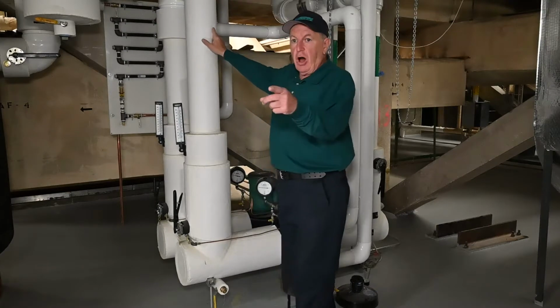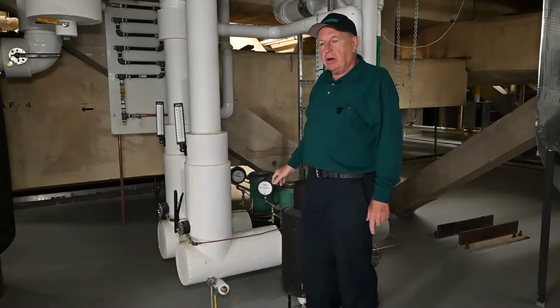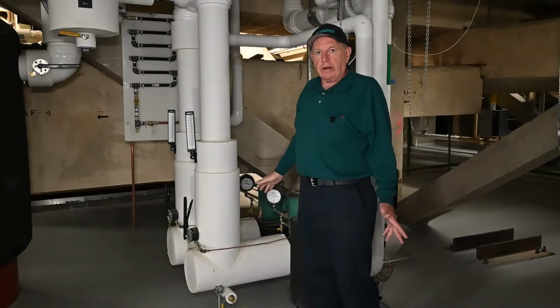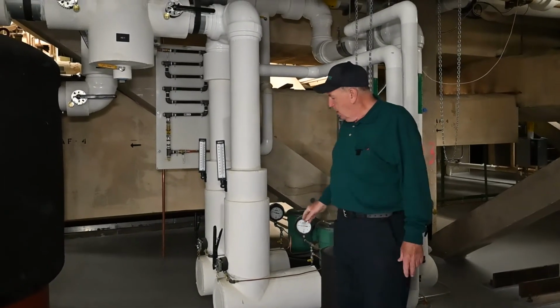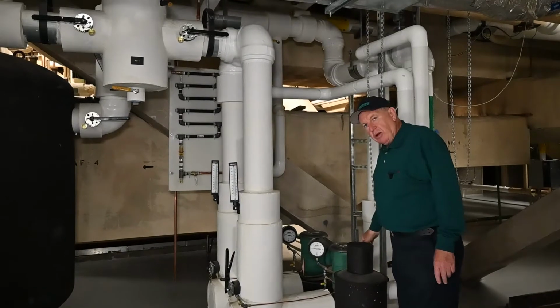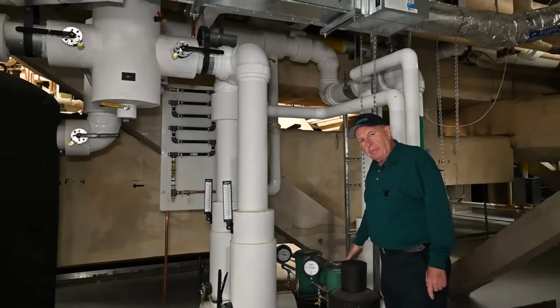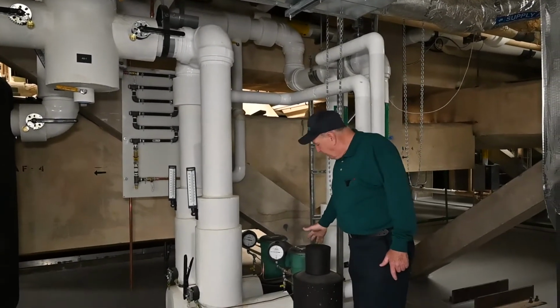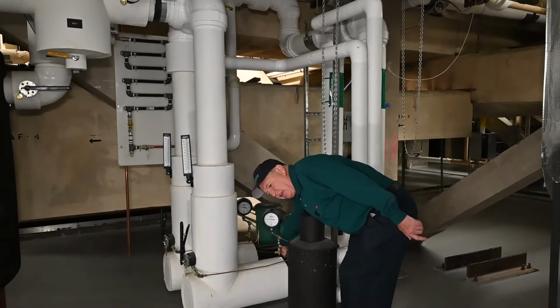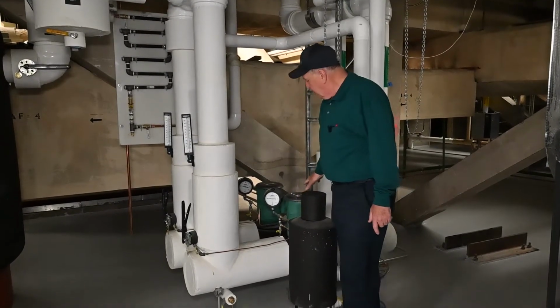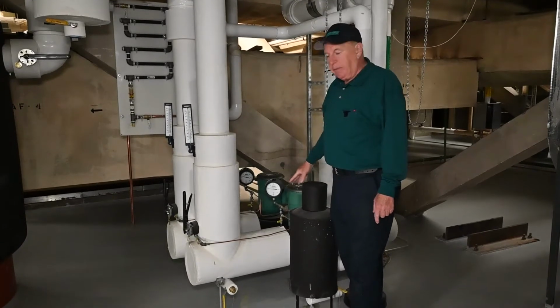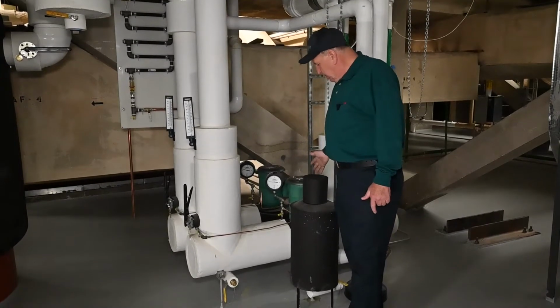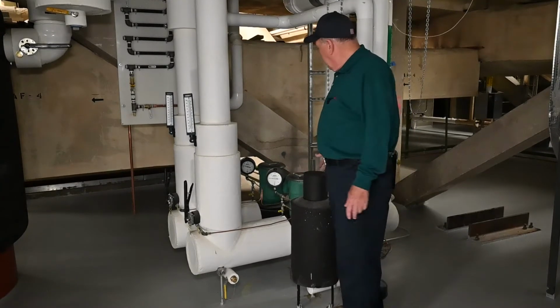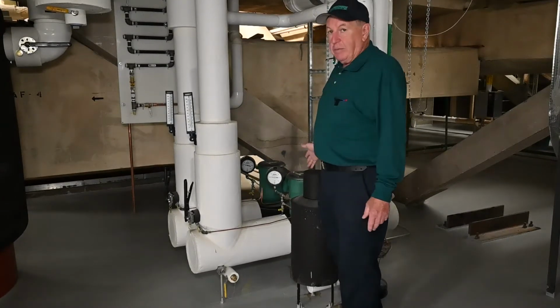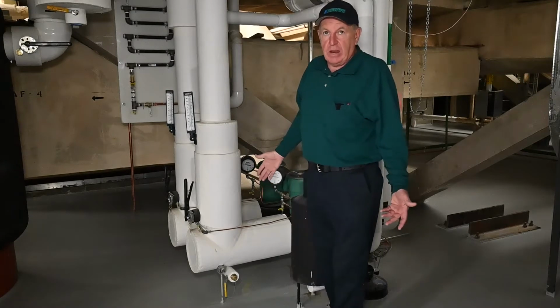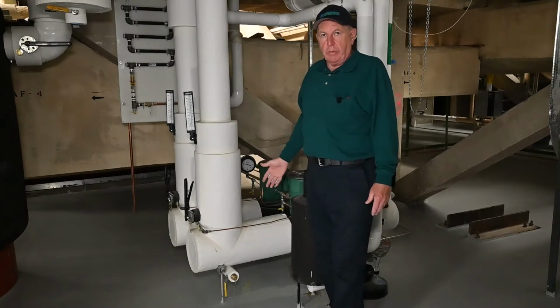There's a makeup glycol pump over there that maintains the pressure in the system. They don't make up with city water. You have to make it up with glycol. They're mechanical seal pumps, so they have a bearing lubrication line, a 1/4 inch lubrication line, and that's open all the time. They're fully insulated because it's chilled water. There's not much else to them, because if you didn't have the glycol in there, you would have to worry about water treatment.